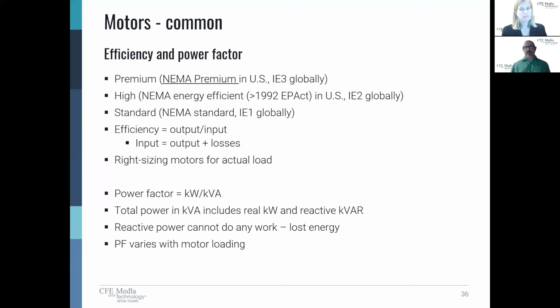Now, you can correct that in a variety of ways. I didn't mention this, but synchronous motors actually have the benefit of having a near unity or maybe even a leading power factor. So if you have a plant with a bunch of induction motors that typically are lagging, you could actually have synchronous motors for some applications, configure them to be leading and get power factor correction inherent in the motor selections that you made.